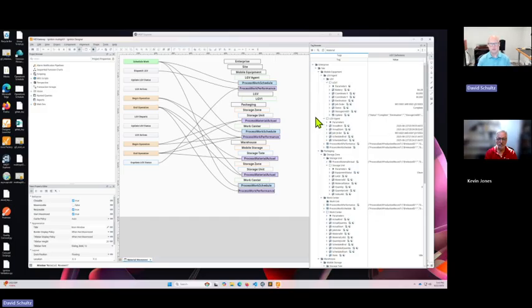And then, of course, those names will change, like line and cell, depending on what type of manufacturing process you are, whether it's batch or continuous or discrete. So those are really the main three that you're looking at. Those names will change a little bit, mostly because that's how they were referred to in those types of industries prior to that happening. So that's going to be the standard that we use for this type of event-driven architecture, where we're going to have channels and we're going to have payloads. This is the same thing as topics in an MQTT broker.